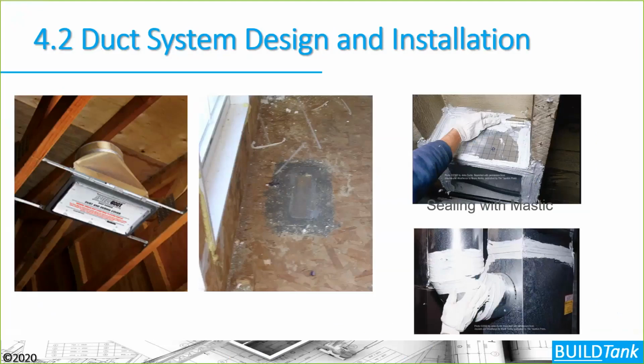If you are using duct systems, they have to be covered and protected during construction. And then after construction, they need to be cleaned. So that's something that you might have to add to your process, is actually cleaning the duct system.